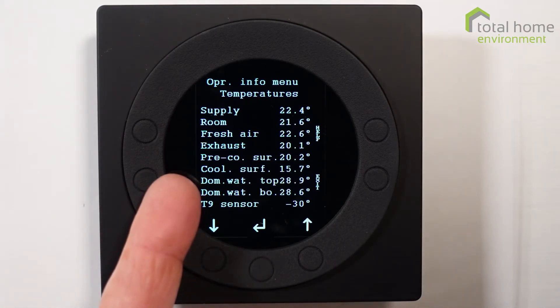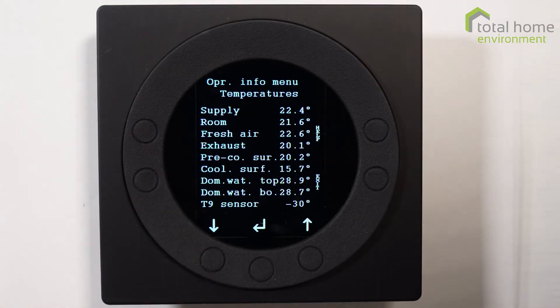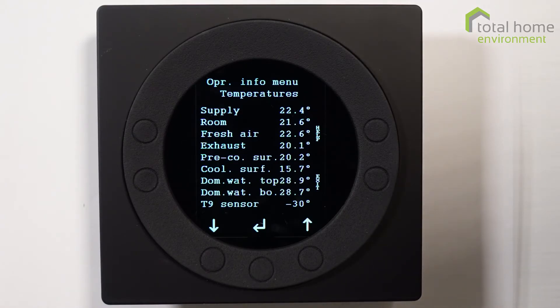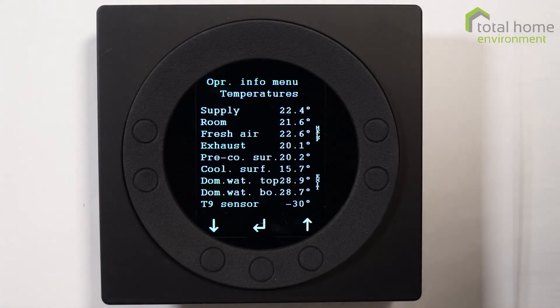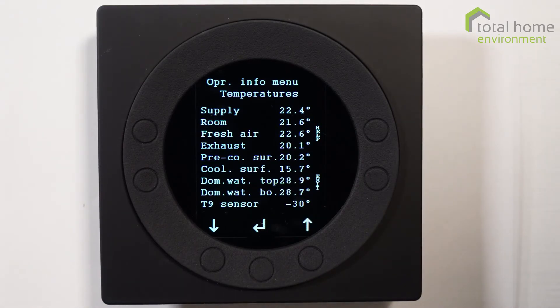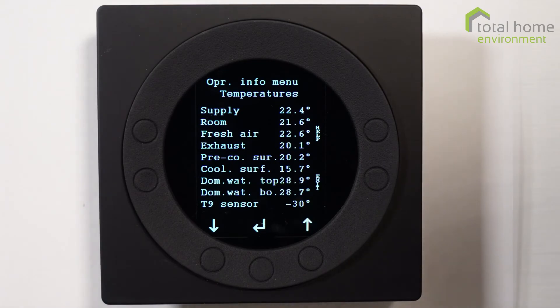The next two down, domestic water top and bottom, are pretty obvious. T9 usually says minus 30 unless we have an additional function added to it, such as an additional sensor for extra heating. If it says minus 30, it means there's no sensor connected and it's not being used.